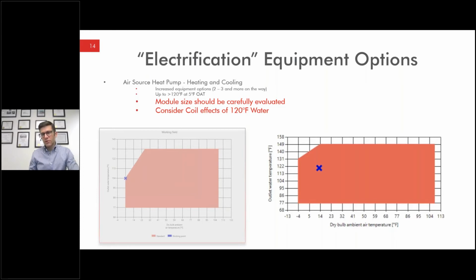The one area where we see a limiting factor is single row fin tube if you have a lot of glass. Single row fin tube with 120 degree supply water can be challenged to heat a high load envelope.